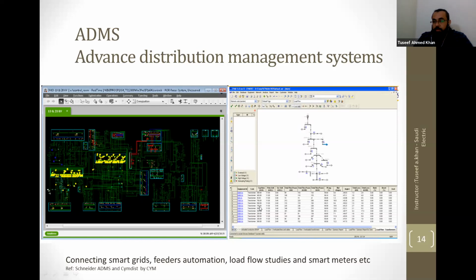You can run many studies with this type of software. In K Electric, my previous company, we used network reconfiguration on some feeders. This network reconfiguration tool is very important—if your data accuracy is high and you implement network reconfiguration across your whole network, it will immediately give you good normally open points. Implementing network reconfiguration results can show a minimum 5% reduction in distribution losses right away.